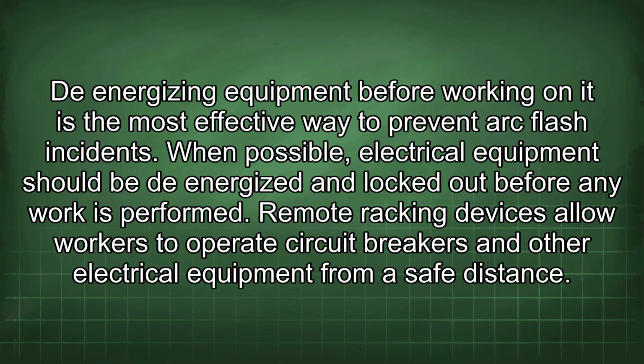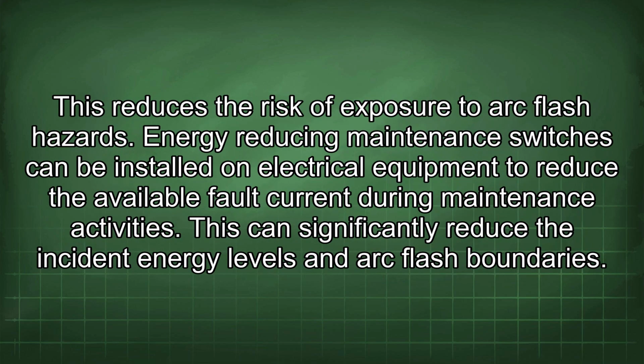When possible, electrical equipment should be de-energized and locked out before any work is performed. Remote racking devices allow workers to operate circuit breakers and other electrical equipment from a safe distance. This reduces the risk of exposure to arc flash hazards. Energy-reducing maintenance switches can be installed on electrical equipment to reduce the available fault current during maintenance activities. This can significantly reduce the incident energy levels and arc flash boundaries.